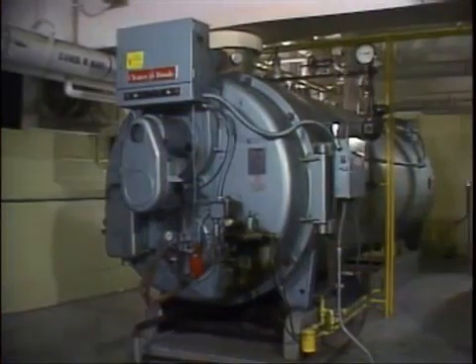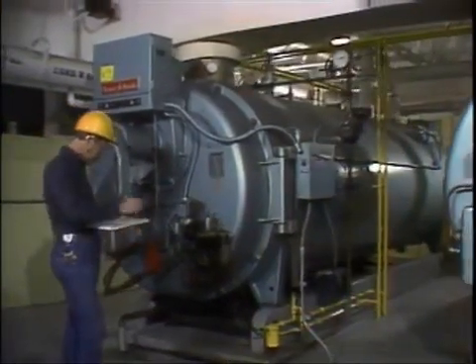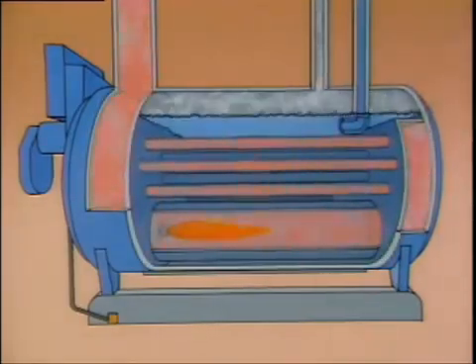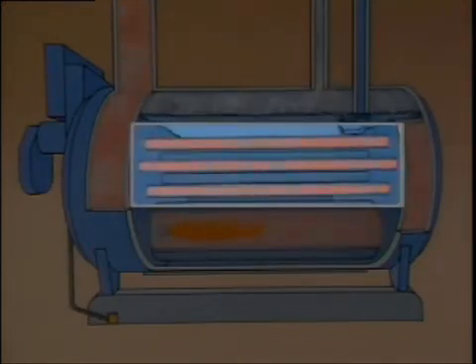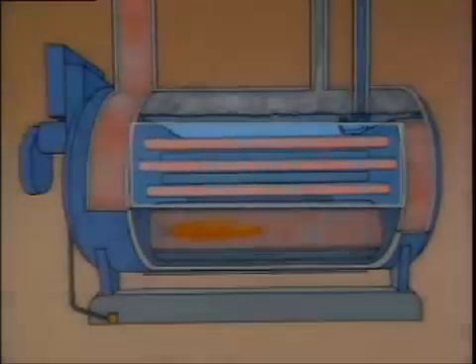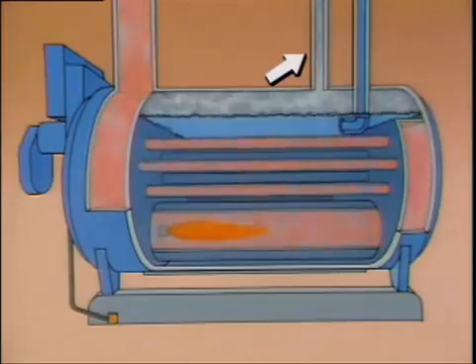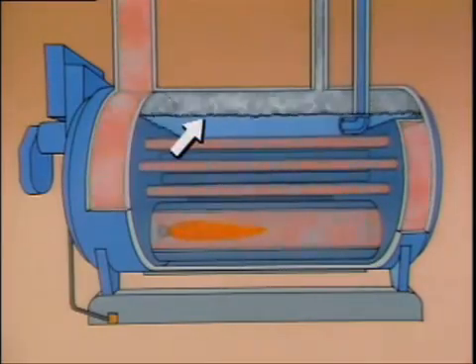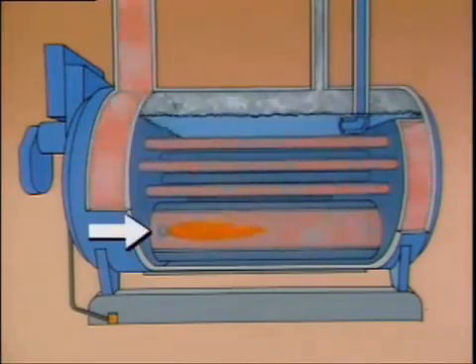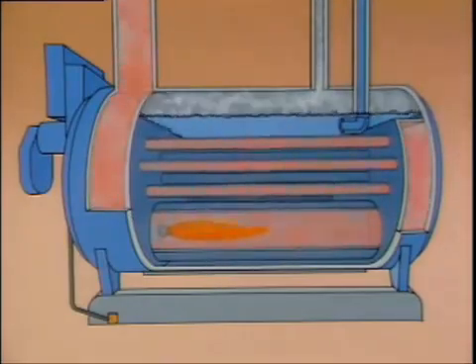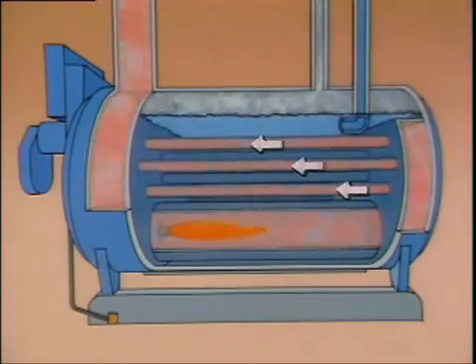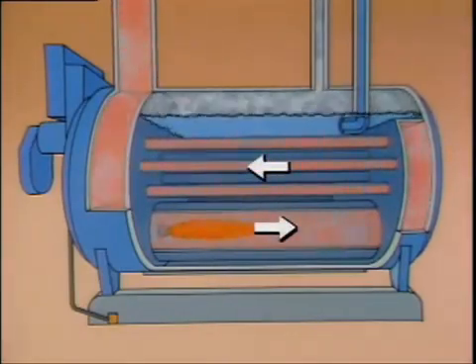Fire tube boilers route hot combustion gases through metal tubes that run through a shell filled with water. Fire tube boilers vary in design, but most operate under similar principles. A group of horizontal fire tubes routes combustion gases through the boiler, with an outlet for the gases, a feed water line, and a steam outlet line. During operation, water enters through the feed water line and the water level is maintained above the fire tubes to protect them from overheating. Fuel and air enter the combustion area. Each time the gases are routed through the shell it's called a pass — the gases pass through two times in this example, so it's a two-pass boiler.